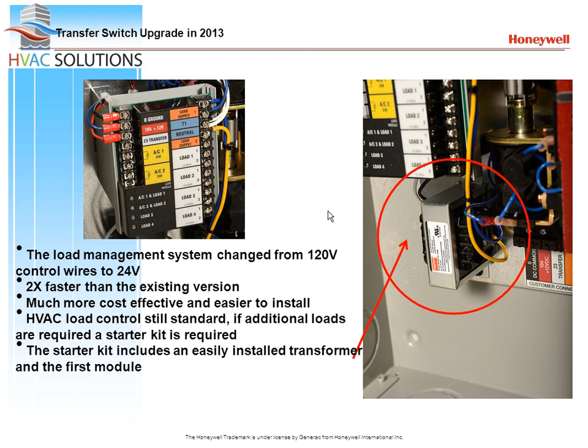This is just a picture of the new circuit board inside of the transfer switch. Basically, what it's showing you is you still need some sort of contactor, which we're calling a DLM module, but you need a transformer, and it makes it a little easier in terms of wiring because we're dealing with 24 volts, not line voltage.